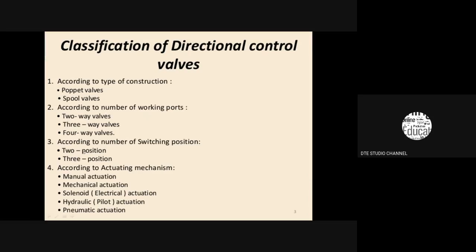For moving the spool inside the valve body, by means of a number of actuating elements like a push button or hand lever or pedal operated or solenoid operated, it may have 2 positions or 3 positions. For moving the actuator in different directions, in some cases 3 positions may be required, and for some actuators 2 positions is enough.